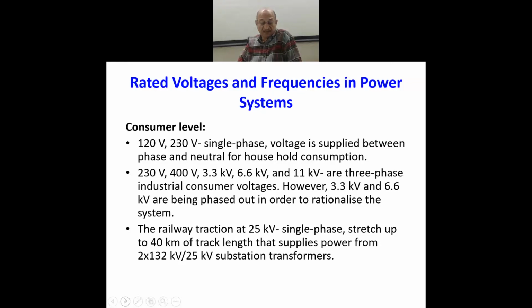We have another standard system of high voltage distribution of power, adopted by the railways practically all over the world. It is being adopted at 25 kV single phase AC voltage. And in the electric traction system, you might have observed while traveling with the trains that every 40 kilometers there is a substation which supplies the power to all the locomotives in that range of 40 kilometers, 20 kilometers on either side of the substation.